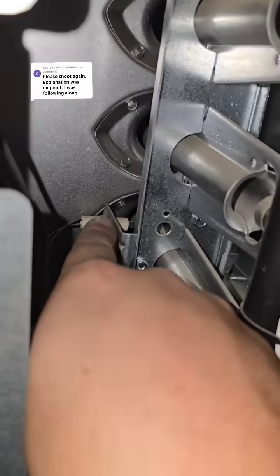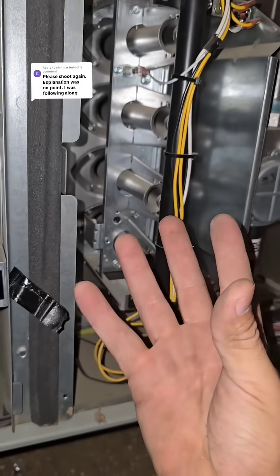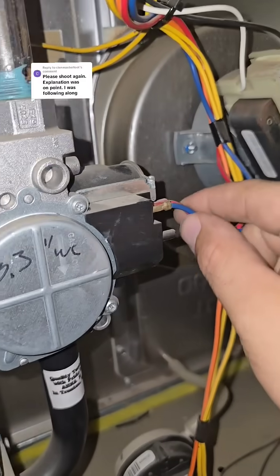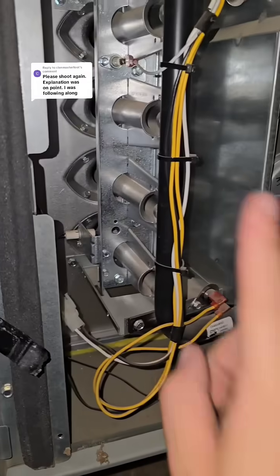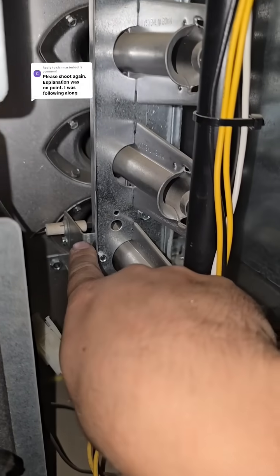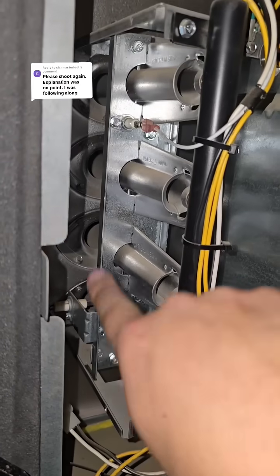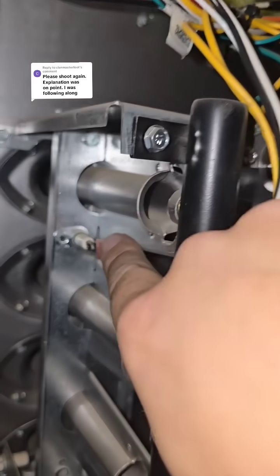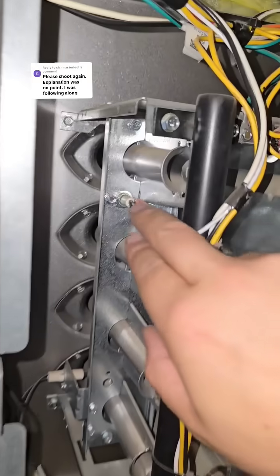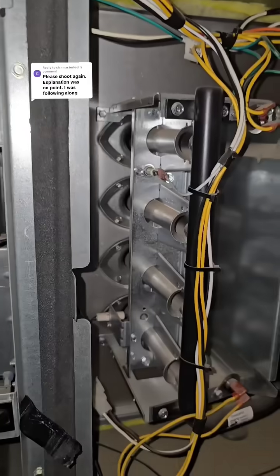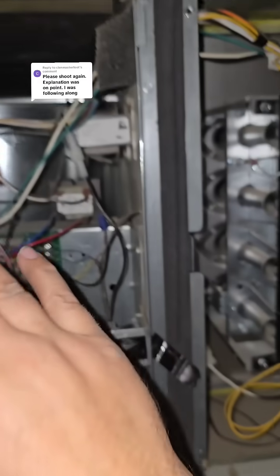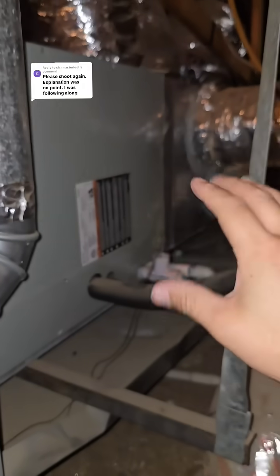Once the board registers all the switches are working just fine, it's going to allow the igniter back there to glow really hot and red. And then the board will send 24 volts over to your gas valve and it'll open it. Once the gas valve opens, it'll shoot gas out this first burner and light, and then it'll carry from each and every one of these burners. Once it gets to the last burner, there's a flame sensor right here. Can you see it? That sensor? That flame sensor will sense if there is a flame or if there isn't a flame, so it's not just spitting gas out. Once that flame sensor senses that there is a flame, it'll allow this blower motor to kick on and run across the heat exchanger, which is what's going to make the air really, really hot.